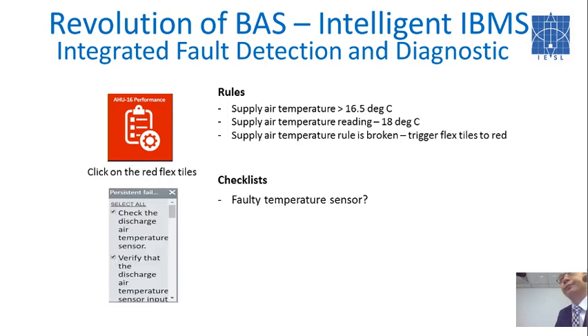The checklist appears. So these are some examples of the checklist itself. Is the temperature sensor faulty? You need software offsetting, or you need to change the sensors. Is the leaving temperature for the chilled water too high? That causes the supply air temperature to increase. So if that's the case, the chiller itself is having some problem.